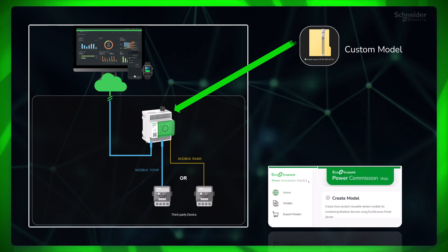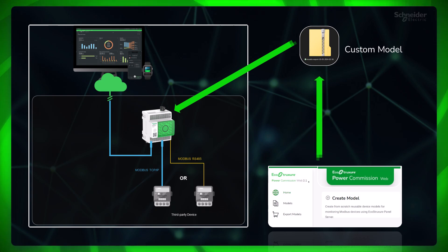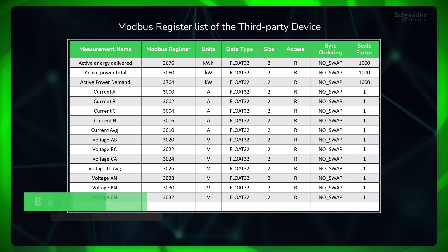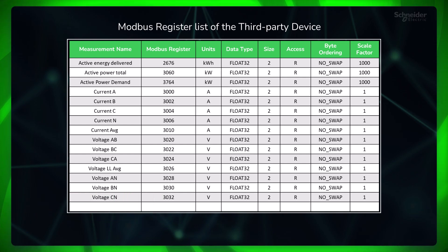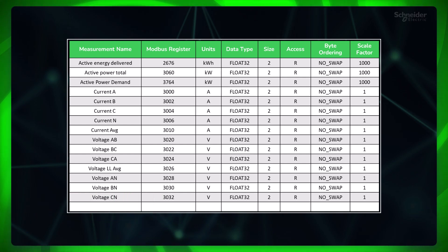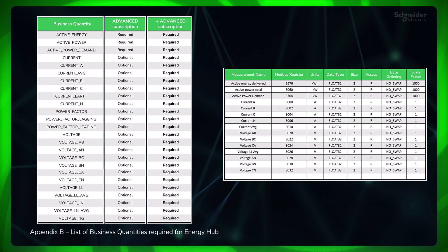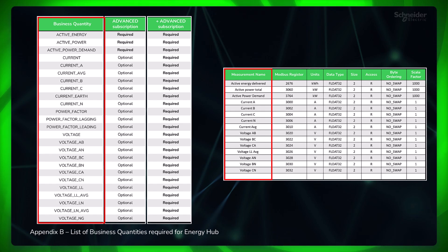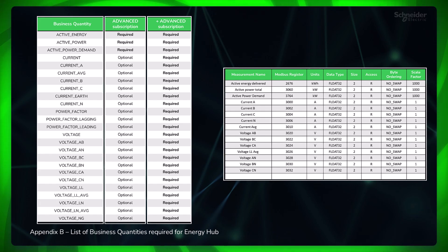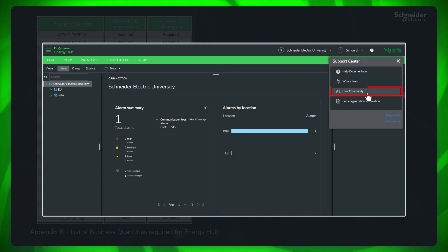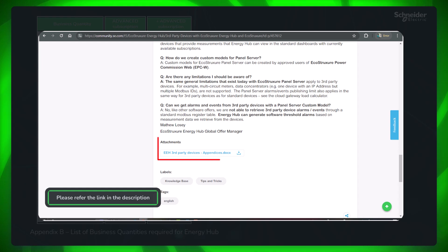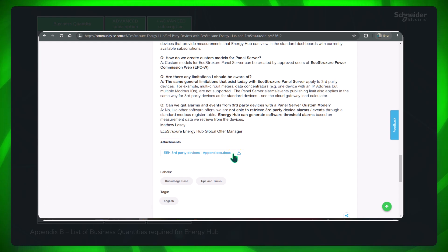To create and export custom models for Panel Server, EcoStruxure Power Commission web tool is used. Before getting started, please be ready with the Modbus register list of the respective third-party device. In the device register list, please make sure the required business quantities for Energy Hub are available to show proper data in the screens and dashboards as per the subscription. For a detailed list of business quantities and corresponding measurements, please go to the user community and refer to this post.